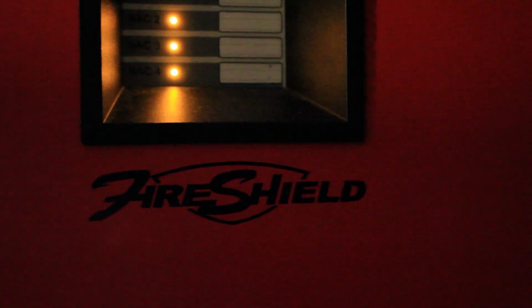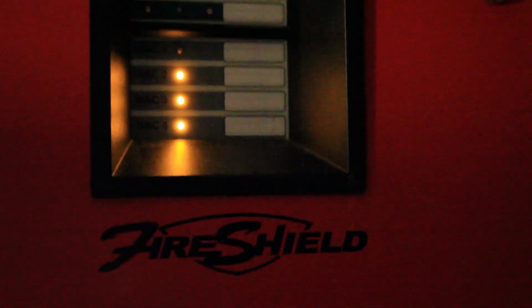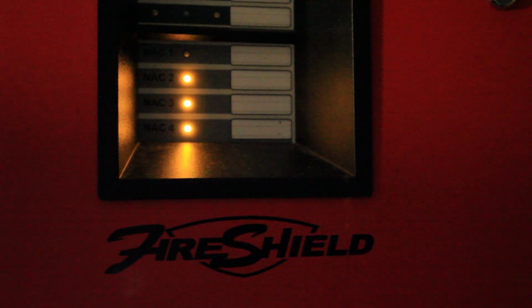Yep. So for the first time we have an all EST pull station setup, and we have our EST panel with a FireShield FS 1004, and we'll see there are troubles on NAC 2, 3, and 4, which I will get into. And hey, there's a trouble on zone 4, which has been there, but I will come into that in a moment.